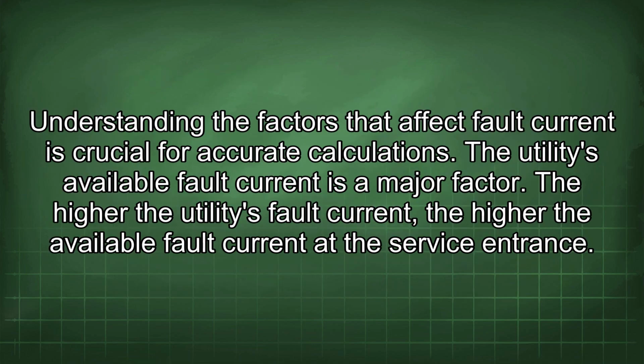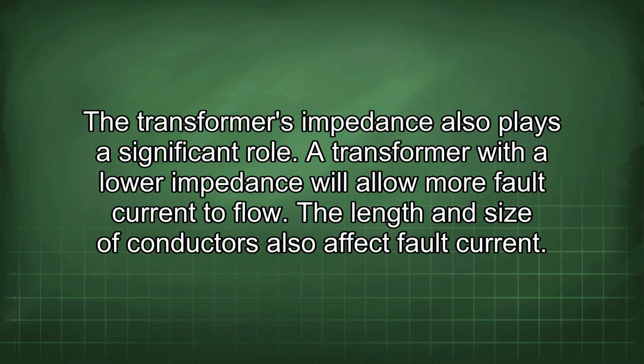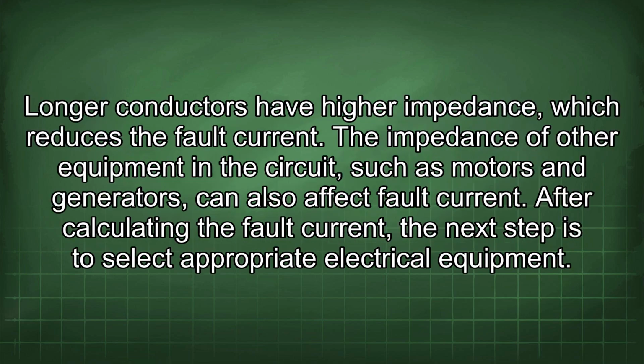Understanding the factors that affect fault current is crucial for accurate calculations. The utility's available fault current is a major factor. The higher the utility's fault current, the higher the available fault current at the service entrance. The transformer's impedance also plays a significant role. A transformer with a lower impedance will allow more fault current to flow. The length and size of conductors also affect fault current. Longer conductors have higher impedance, which reduces the fault current. The impedance of other equipment in the circuit, such as motors and generators, can also affect fault current.